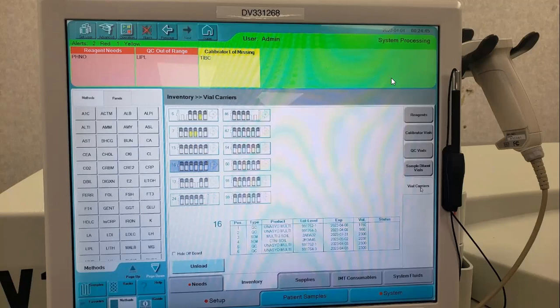So with the vial carriers, there's different colors. If they are white, that means they have enough level, they're within their expiration, they might have just got put on. So those white ones are good to go. If they are yellow, it means that the reagent is getting close to expiration, or the level volume is getting low and it might be a good idea to consider removing them.